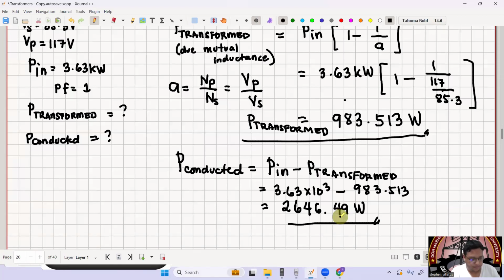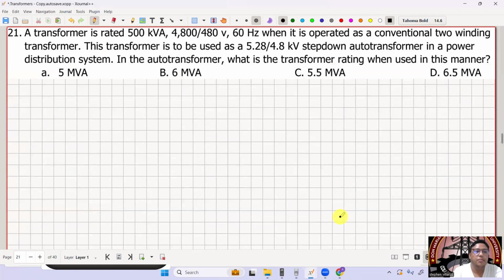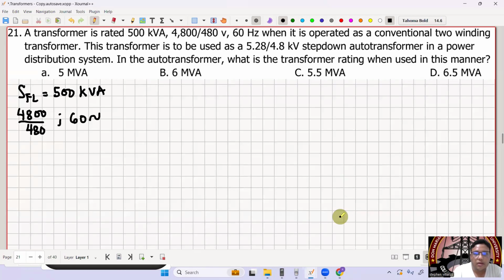So next tayo, number 21. So we have a transformer rated, yung ating SFL that is 500 kVA, given that your voltage is 4,800/480 volts, 60 hertz, operating as a conventional two-winding transformer. Now, this transformer is used or is to be used as a 5.28/4.8 kilovolt step-down transformer.